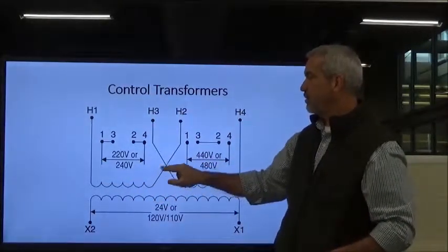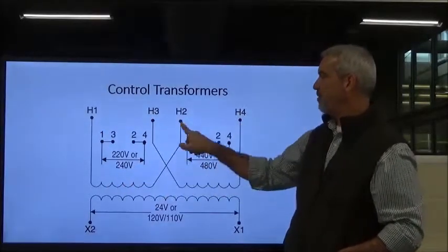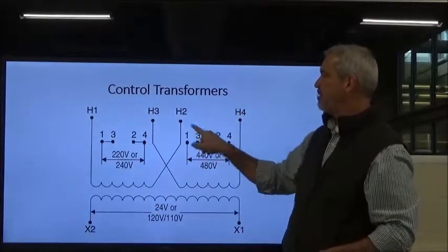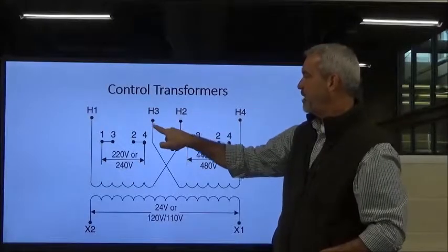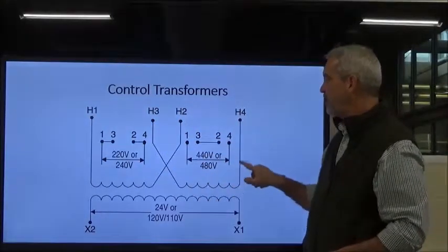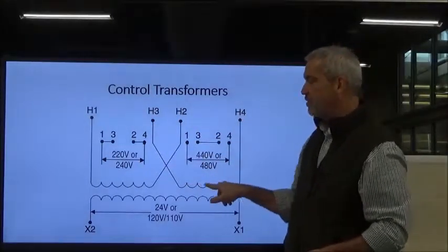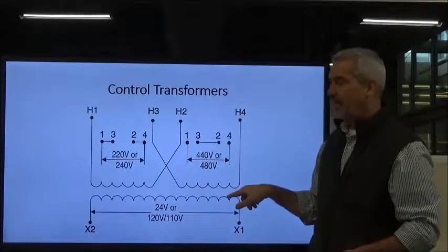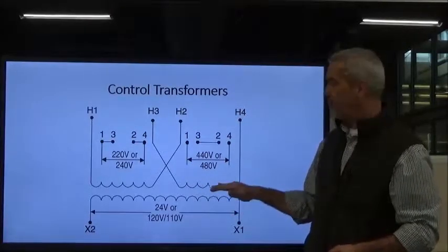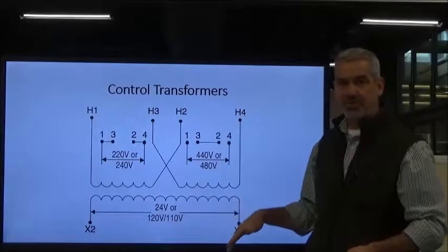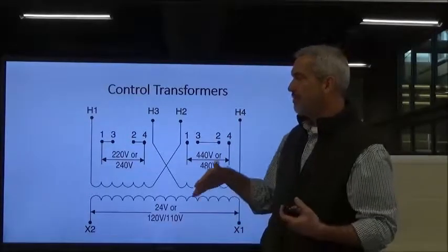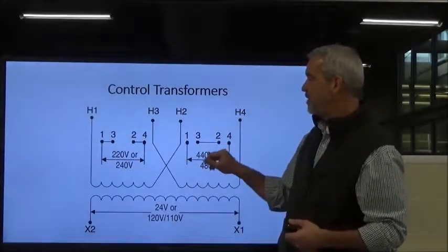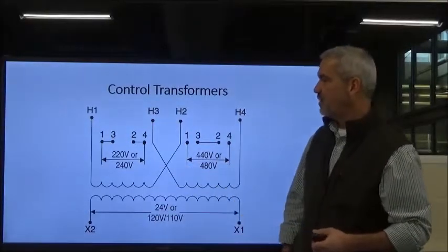We're going to come power into H1, go to H2, jumping between 2 and 3, and then continue on. That has put these coils, these turns, in series with one another, so we've increased the resistive load of our transformer. For a higher voltage, we go with it in series; for a lower voltage, we're going to go with it in parallel.